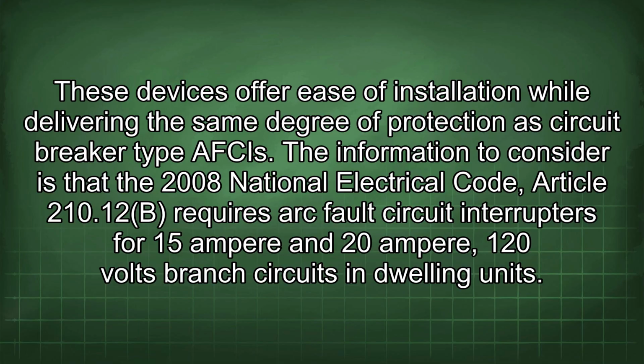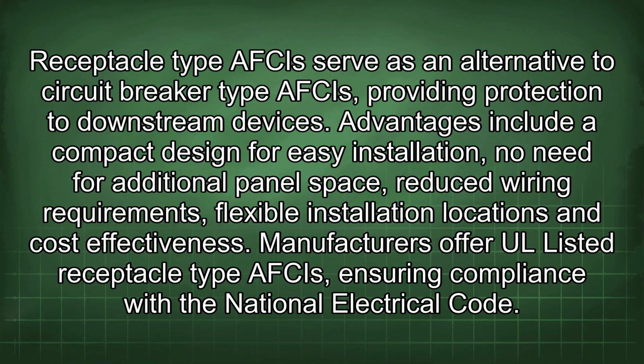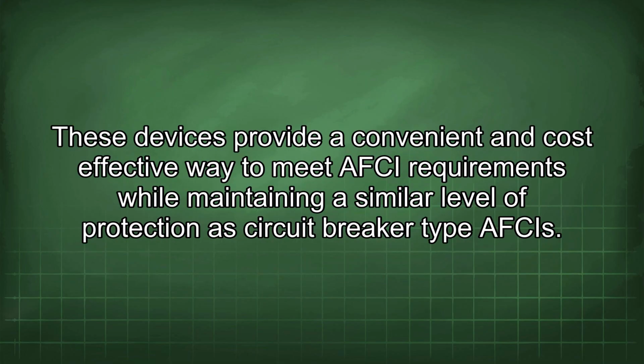type AFCIs. The information to consider is that the 2008 National Electrical Code, Article 210.12(B), requires arc fault circuit interrupters for 15 ampere and 20 ampere, 120 volt branch circuits in dwelling units. Receptacle type AFCIs serve as an alternative to circuit breaker type AFCIs, providing protection to downstream devices. Advantages include a compact design for easy installation, no need for additional panel space, reduced wiring requirements, flexible installation locations, and cost-effectiveness. Manufacturers offer UL-listed receptacle type AFCIs, ensuring compliance with the National Electrical Code. These devices provide a convenient and cost-effective way to meet AFCI requirements while maintaining a similar level of protection as circuit breaker type AFCIs.